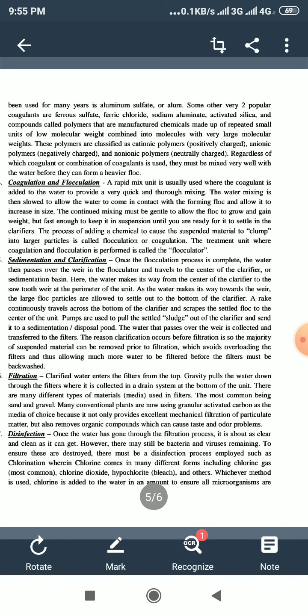Some other very popular coagulants are ferrous sulfate, ferric chloride, sodium aluminate, activated silica, and compounds called polymers — manufactured chemicals made up of repeated small units of low molecular weight combined into molecules with very large molecular weights. These polymers are classified as cationic polymers (positively charged), anionic polymers (negatively charged), and non-ionic polymers (neutrally charged). Regardless of which coagulant or combination of coagulants is used, they must be mixed very well with the water before they can form a heavier floc.